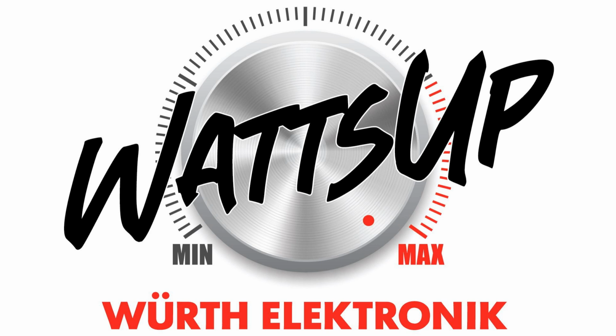The next ones are the RTDs. These are widely known as the PT100 and PT1000 ones. You must know them from the cylindrical types, or nowadays they are also available in SMD types. They are very accurate and they are also linear. But on the other hand, they are highly expensive. So very high accuracy also comes at the cost of price.